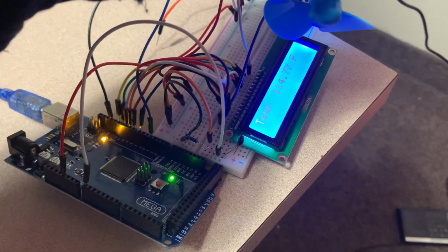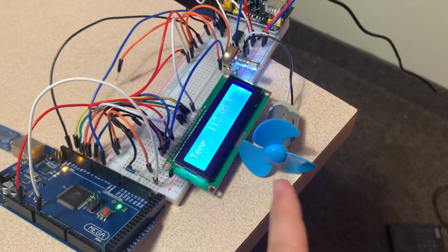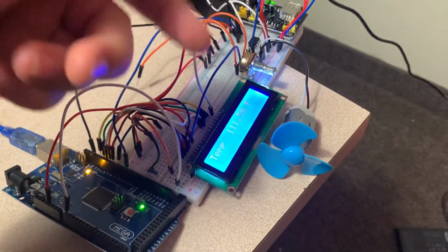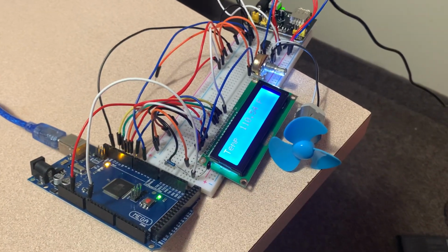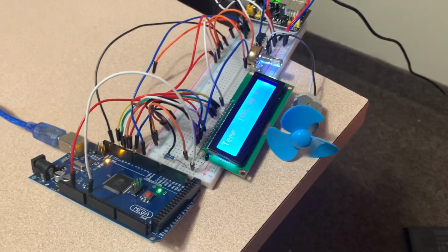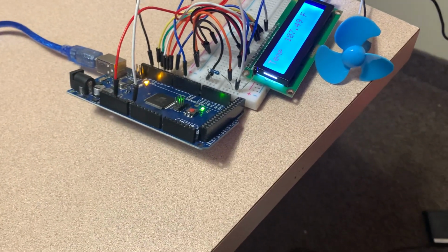This is another issue that has arisen. It really has to do with the power. Since the fan turning on takes a lot of power, it actually takes power away from the screen itself, and it takes power from the resistor, therefore making the temperature lower than 115, and then of course that turns the fan off, and that gives more power to the resistor, turning the resistor back up, and you get this oscillation sort of error. But it still works. Obviously, it keeps cooling until the temperature has gone down significantly.